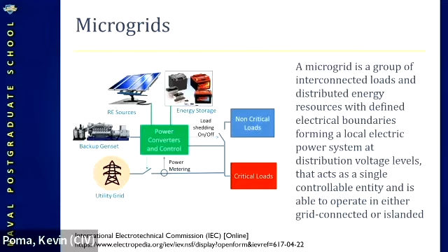Right, yes, of course there's the issue. If we go back to the picture, when you have a microgrid with power loads and you have a fault on the grid, you need to make sure you open the switch, because when PG&E sends people to work on the power line, knowing the lines are down and there's no electricity, but you're backfeeding power from your solar panels and your energy, it's a problem. So there has to be contracts in place with the utility company to be allowed to have a microgrid. You need certain mechanical switches you can open to make sure you're really disconnected from the grid when you continue to operate independently. This is one technical aspect Professor Fouts was pointing out, but there are also political and logistical aspects in addition to the technical one.